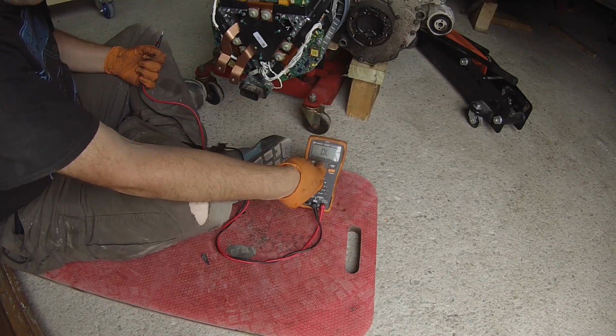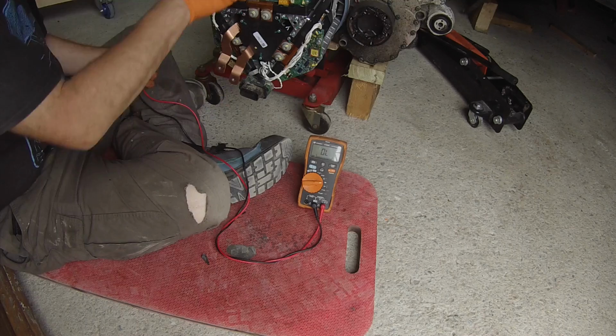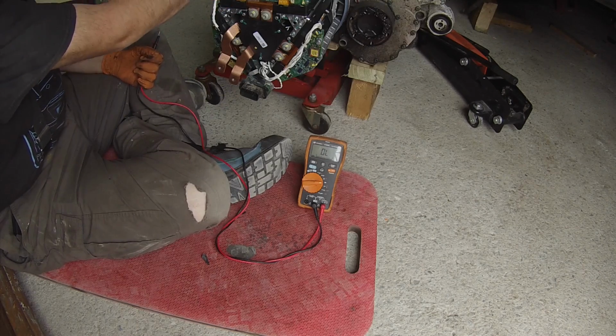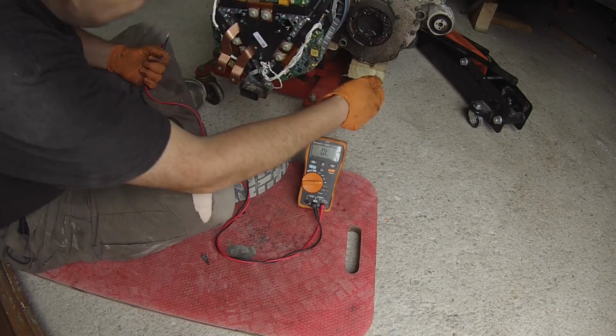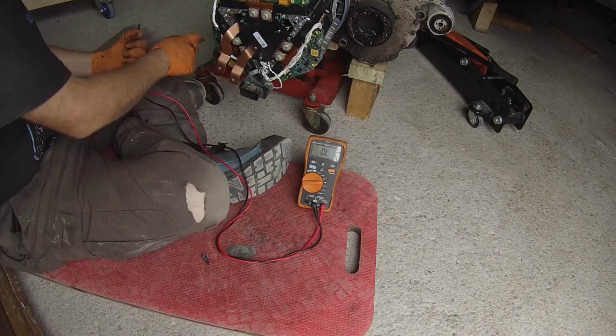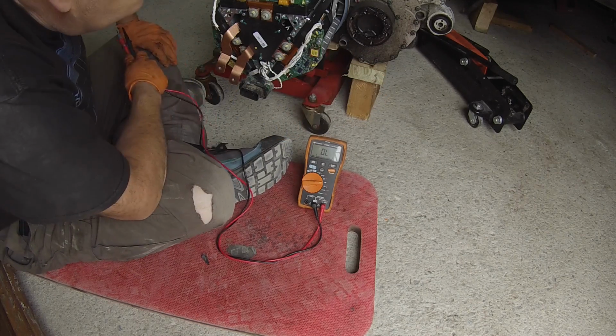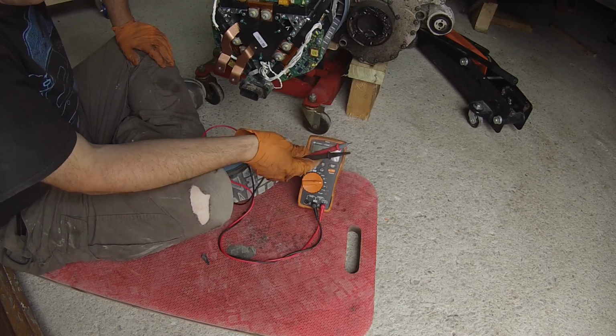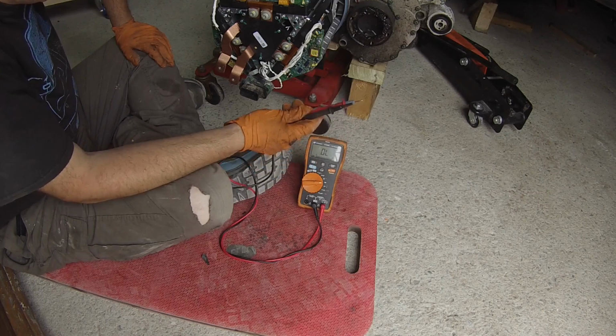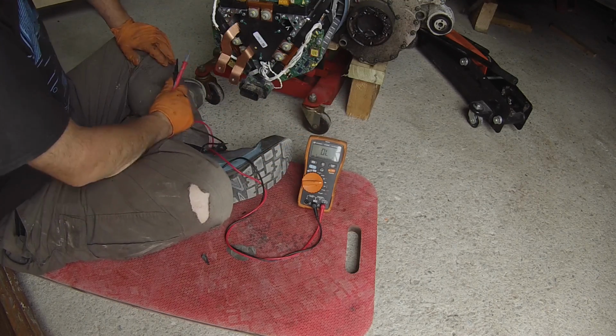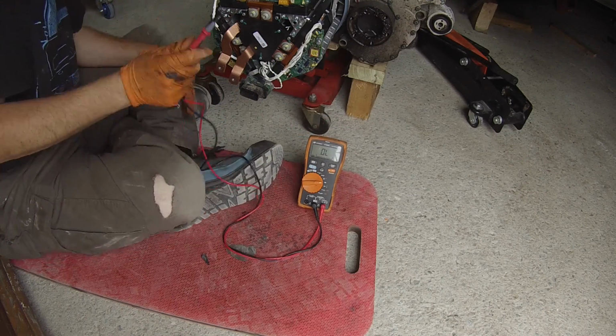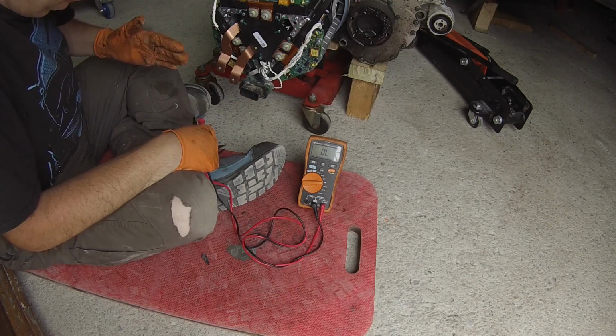What that tells us is that there's no horrific short circuits on our DC bus. And the reason we saw the voltage increasing here was our capacitors, of which there are 3, have charged up to the little bit of voltage that our multimeter provides to us. Now, that's good.